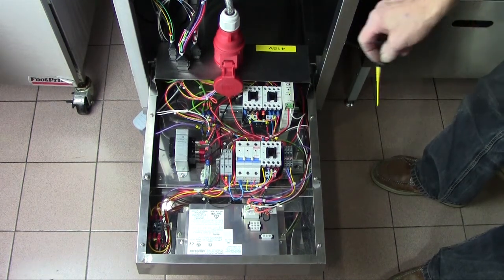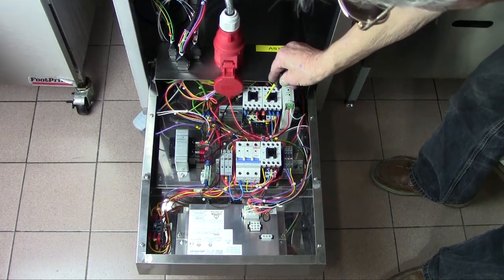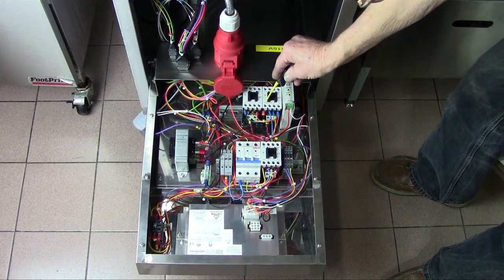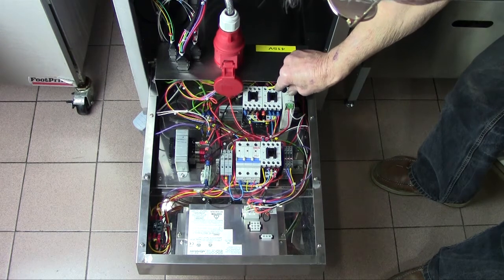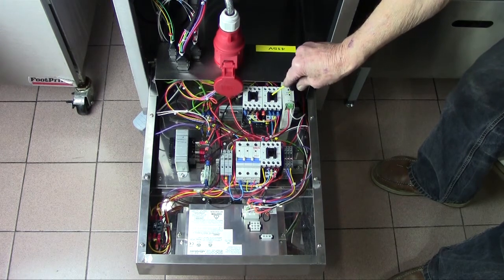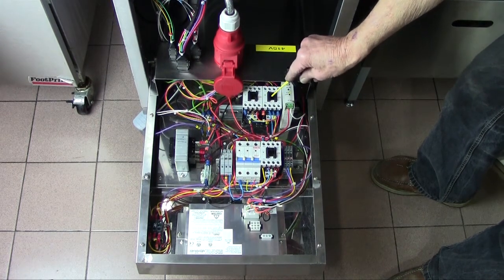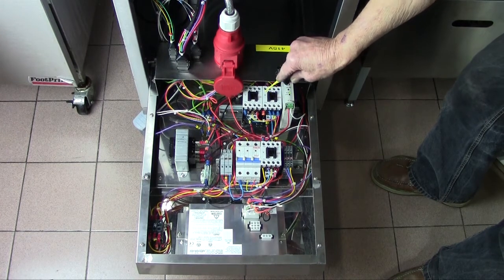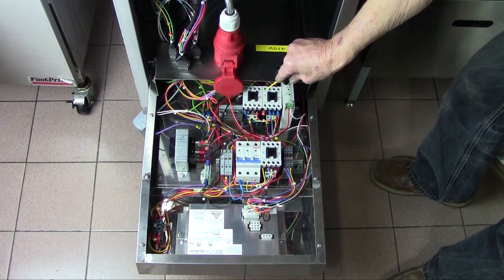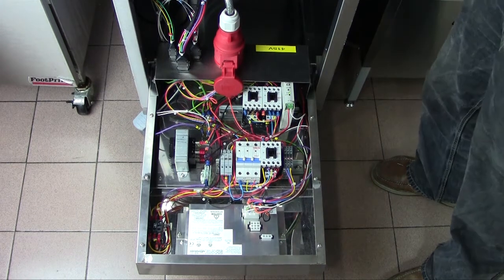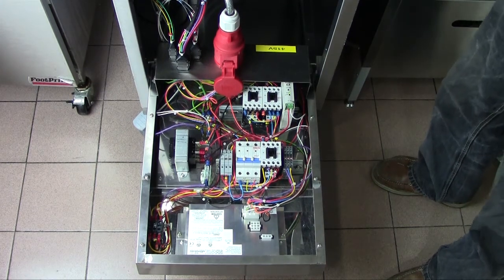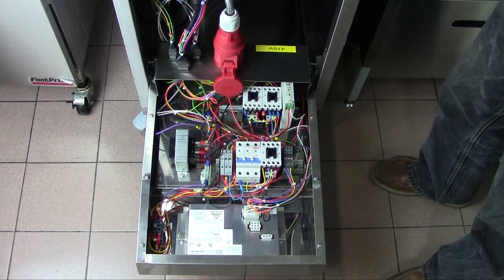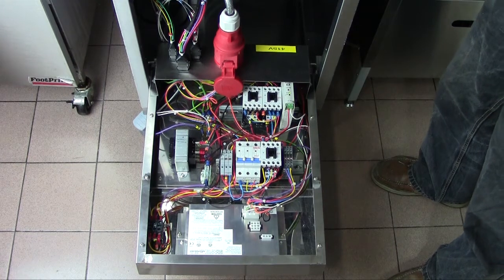With the contactor running, check that there is voltage in and out of the contactor on all three phases. If there is voltage in and out, then check connections to the elements. If the voltage is at the elements and the elements are cold, replace the elements.